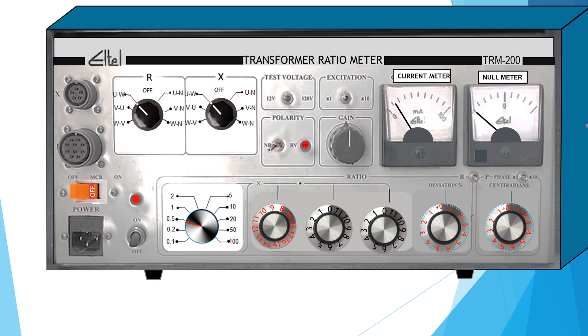By tuning this knob, the pointer of null meter is adjusted at zero mark to obtain a reading, and the reading related to the knob is taken as percentage deviation of TTR.